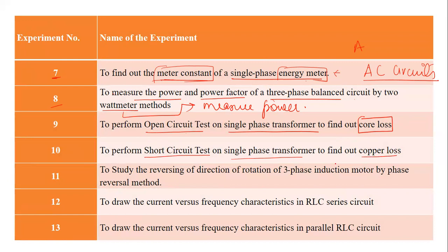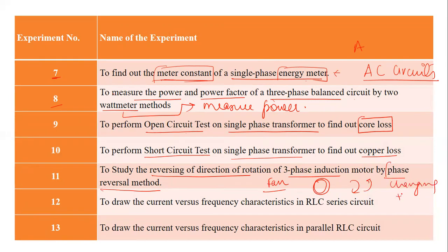After that, we will see how to reverse the direction of rotation of a three-phase induction motor by a method known as the phase reversal method. Generally, AC motors like a fan rotate in the same direction. But using the phase reversal method, we can reverse the direction. As far as a DC motor is concerned, reversing polarity reverses the direction, but for an AC motor, we need the phase reversal technique.